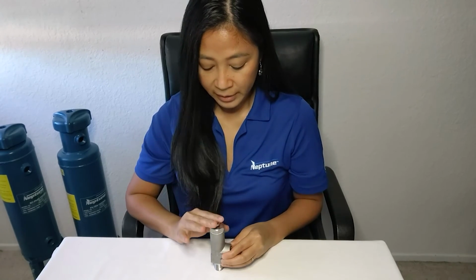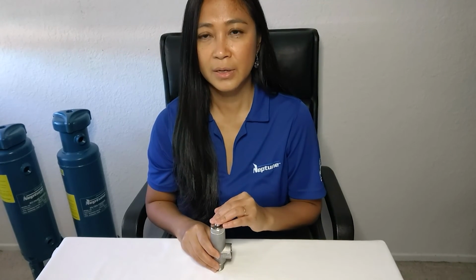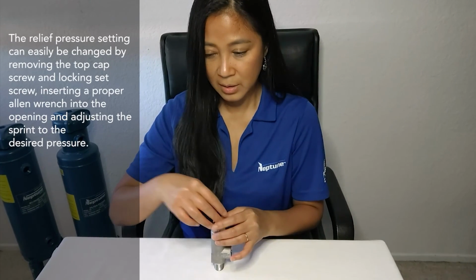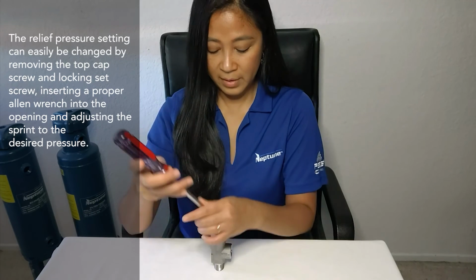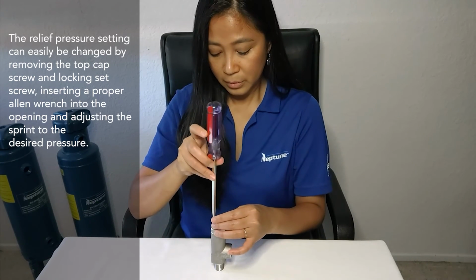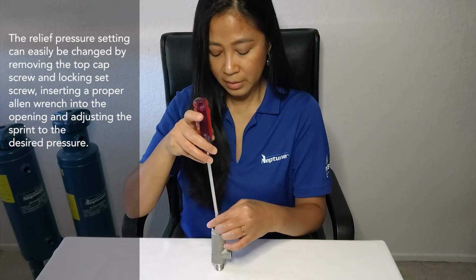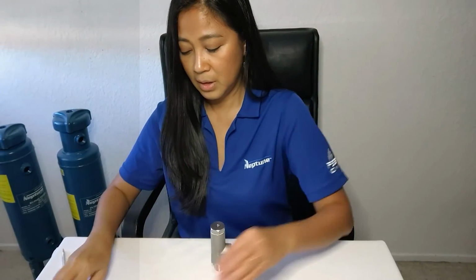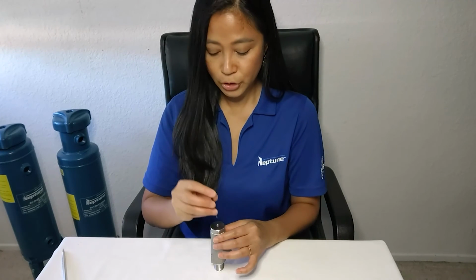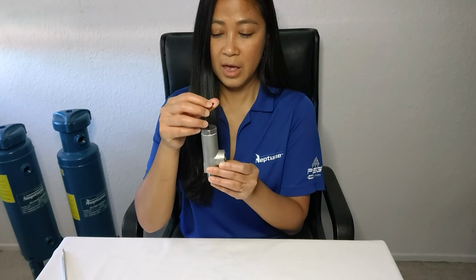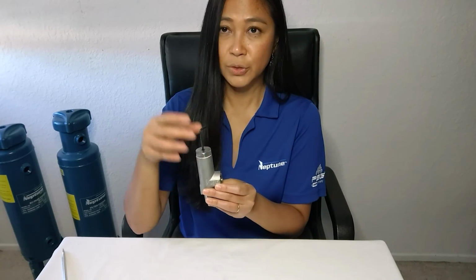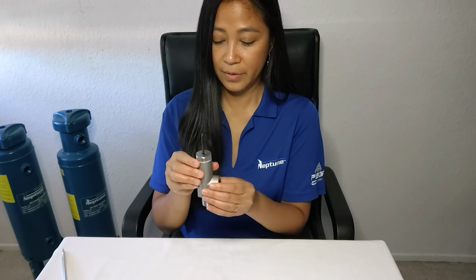With the relief valve, you could adjust the pressure in the field. What you have to do is remove the screw, and sometimes you will need a flat head to loosen it up and take this off. It also comes with an Allen wrench. Then you set the relief valve and make sure it's meeting the certain pressure that you have or the requirement of the system.